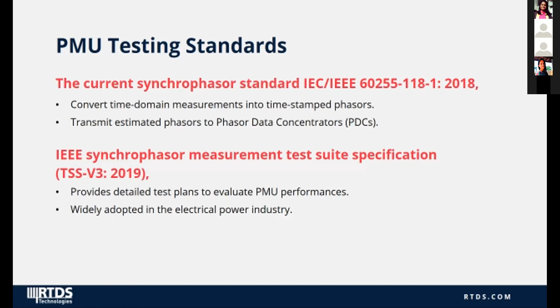First, consider an abstract test system. Here, known input voltage and current signals are fed to the PMU under test with the help of a signal generator synchronized to a common time reference. Then, the PMU's response or measurement is compared against the theoretical inputs. This system can only be realized in a virtual environment such as a time domain simulation tool, where the input test signals and the PMU under test are both implemented in a single entity. A digital real-time simulator is an example of such a simulation tool.